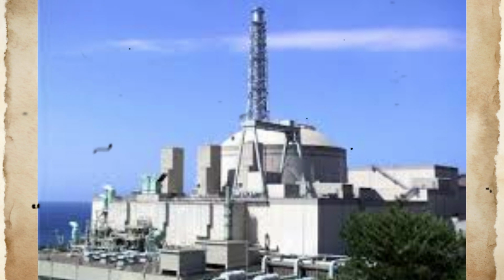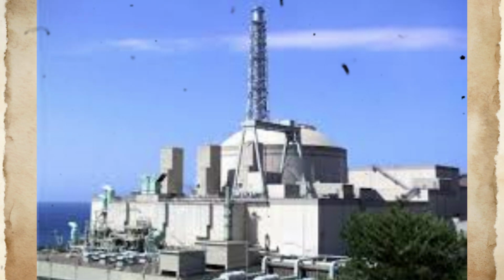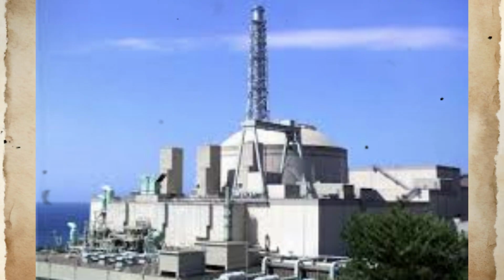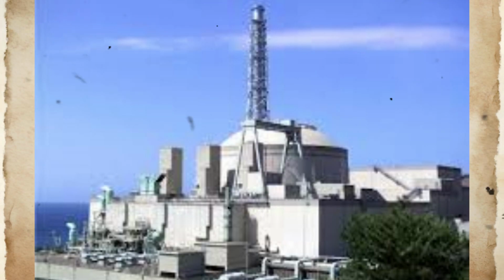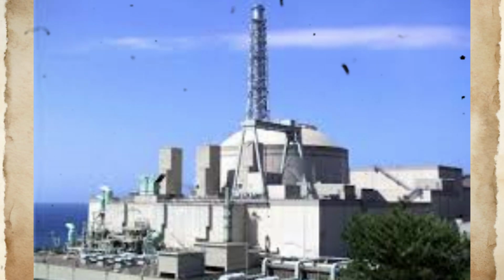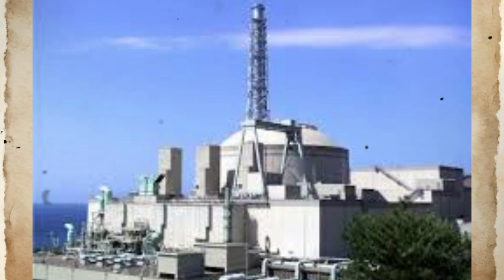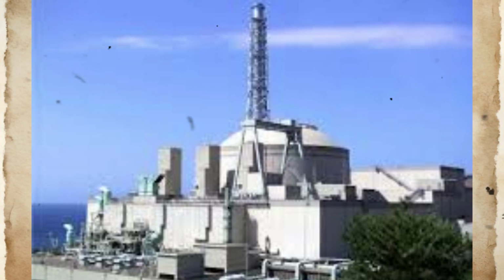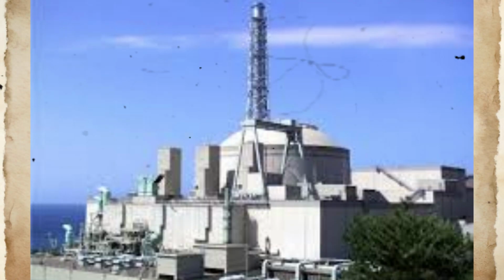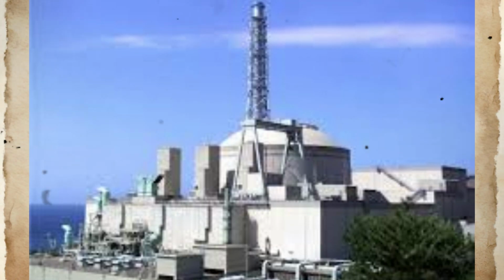All thermocouple wells with comparable geometries were replaced with designs incorporating gradual tapers that prevented vortex formation while maintaining adequate thermal response characteristics. The replacement program required extensive analysis to optimize thermal and mechanical performance simultaneously.